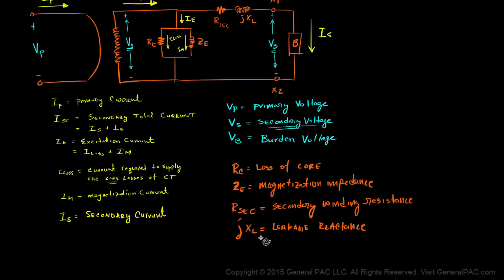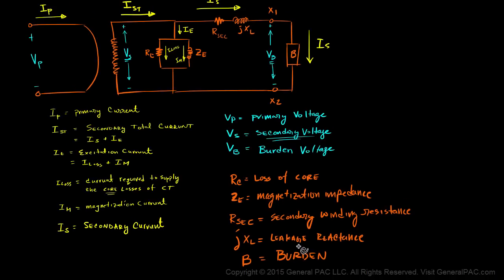Our most important impedance is called B, which is the burden. The burden is essentially all of the impedances connected from the X1 terminal to the X2 terminal — that includes the lead impedance and any relay impedance. If we have a series of relays all connected together, then all of those impedances are added up and are considered the burden of the current transformer.